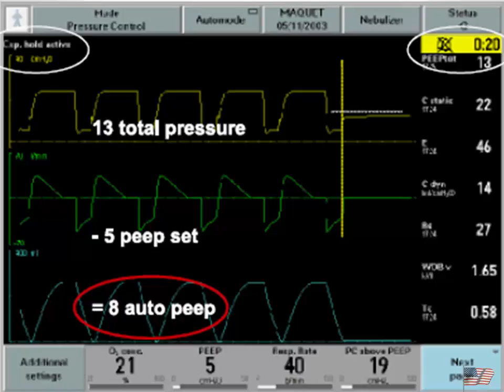And what we normally will see is an alteration where it doesn't come back to baseline. It looks like a leak, but it's not on every breath. If I have this kind of a picture where every breath has the same volume not returning, that's a leak. If I only see that on an occasional breath, that's air trapping, and that's Auto-PEEP being present, or potentially being present. And again, if we measure our PEEP, you can see this pressure rise up. There's an additional amount of PEEP, so I have a set PEEP of 5. I have a total PEEP of 13. That means I must have an Auto-PEEP of 8.